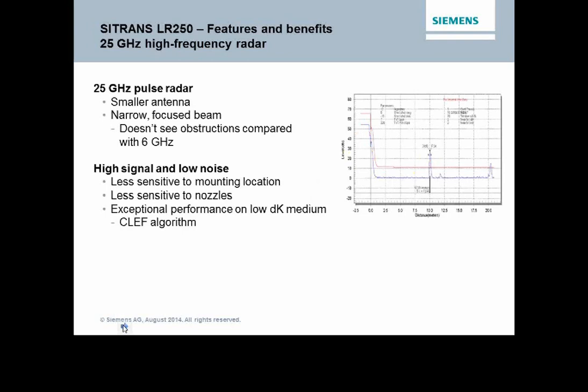Radar by itself, I don't care. You could have a VFD, a variable frequency drive, a noise bomb, right next to these units, and it's not going to affect radar. The frequencies we're dealing with are not affected by that type of equipment. So we have less sensitivity to our mounting location. I'm not worried about things like nozzles, and I can handle low dielectric constant (dK) materials.